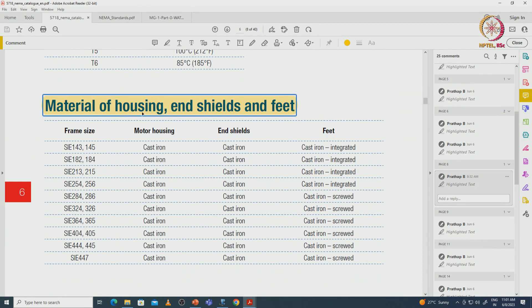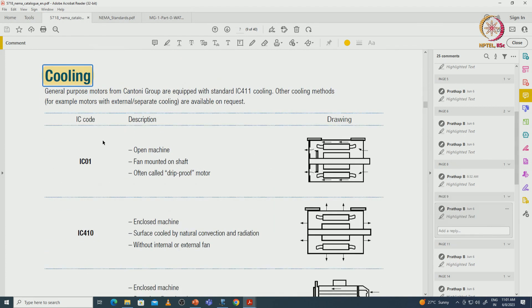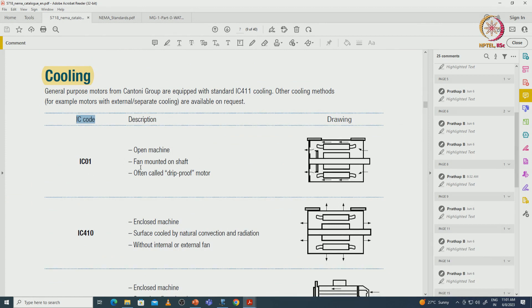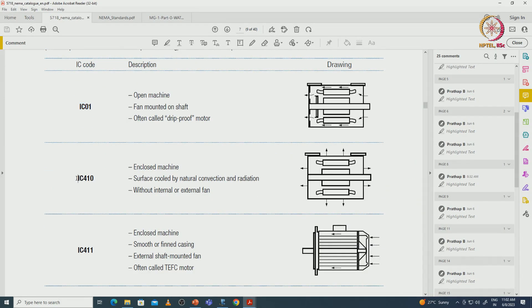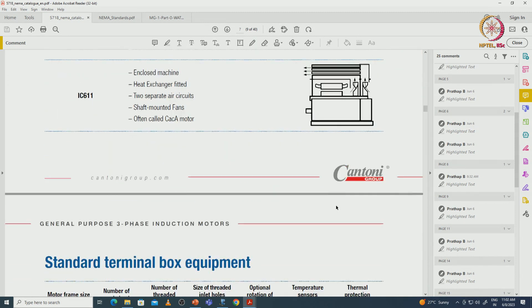Standards also specify materials for housing and end shields. For cooling mechanisms, IEC codes define the type: IC 01 is an open machine with a fan mounted on the back of the shaft. For smaller motors the fan is visible on the back side mounted on the shaft, while larger and higher power rating machines also use shaft-mounted fans. Other standards include IC 410 and IC 411 for different types of cooling.